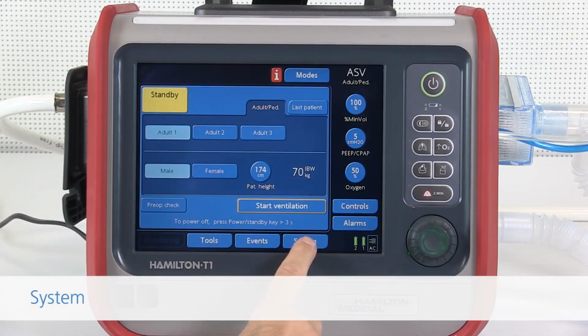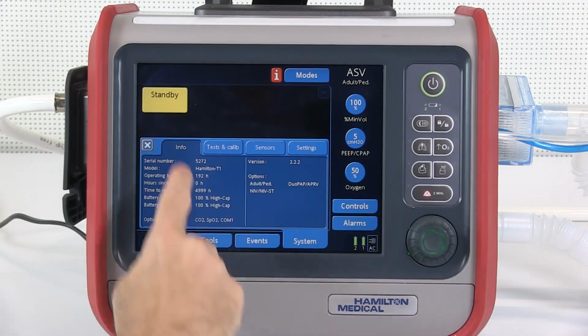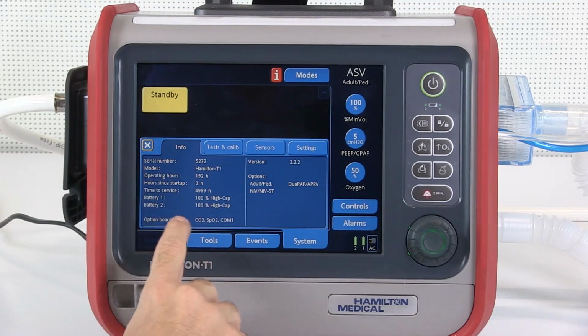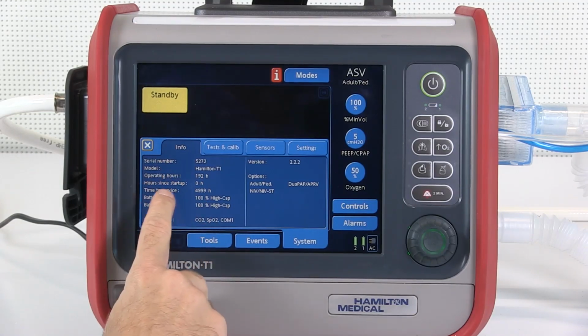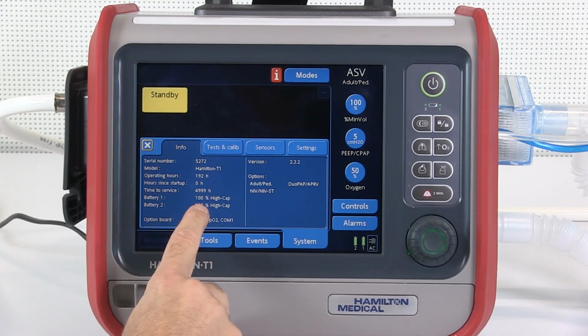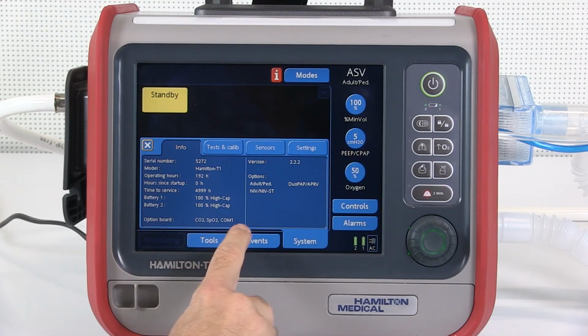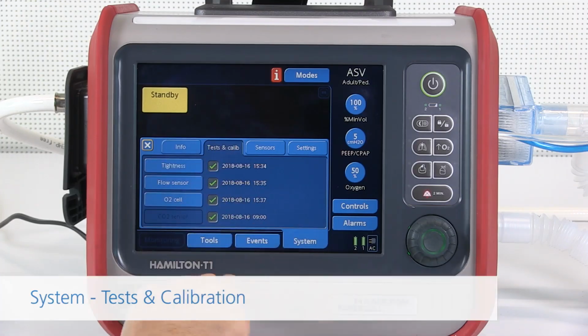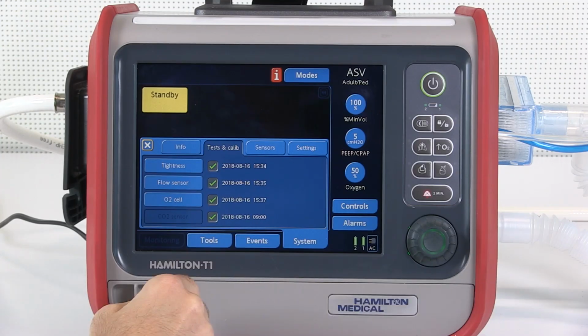Touch System, then Info to view device-specific information including the serial number, model, operating hours, hours since startup, time to service, battery capacity, oxygen consumption, software version, and installed options. Touch Tests and Calibration to perform the pre-operational calibrations and tightness test. See the service software video tutorial where we show you how to perform pre-operational tests.